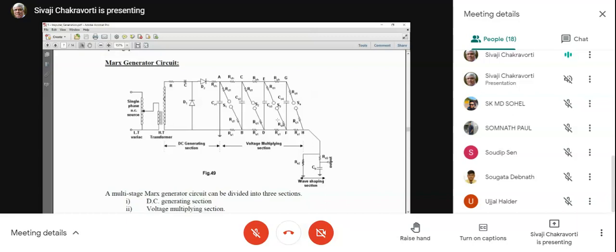at the required voltage, we will trigger the gap of S1 by some means, so that now there will be a cascading effect of voltage, and at the point H we will get 4V. So that now when the charging of CB takes place, it will not be with respect to V, but with respect to 4V. Therefore at the output, we will not get 4V because of the charging of CB. We will lose some amount of voltage. So it will be slightly less than 4V.